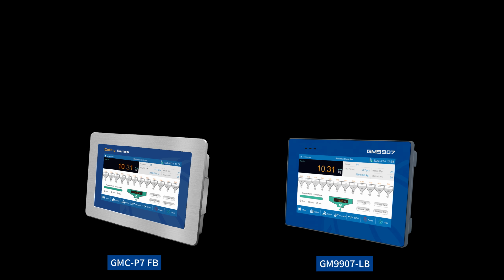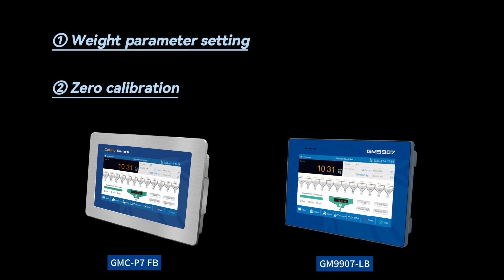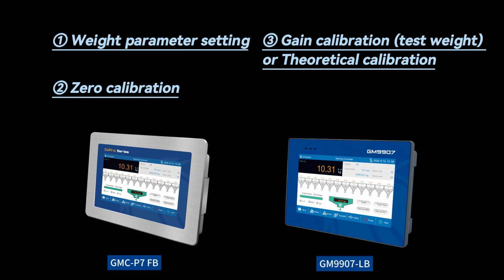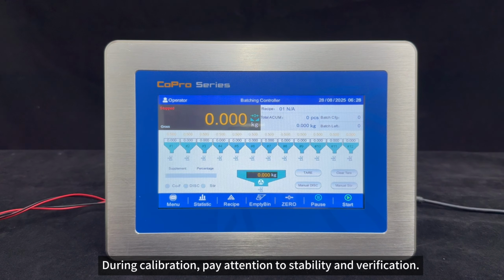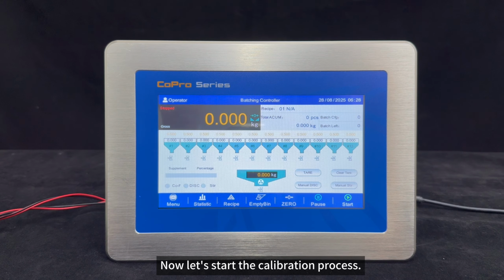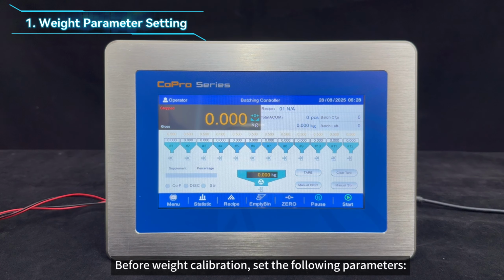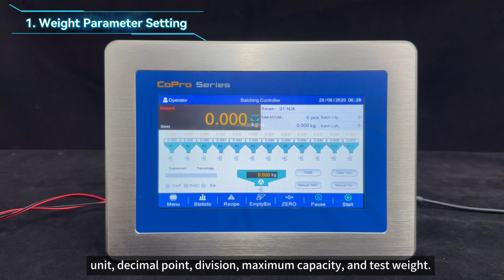The process involves weight parameter setting, zero calibration, gain calibration, test weight, or theoretical calibration. During calibration, pay attention to stability and verification. Now, let's start the calibration process. Before weight calibration, set the following parameters: unit, decimal point, division, maximum capacity, and test weight.